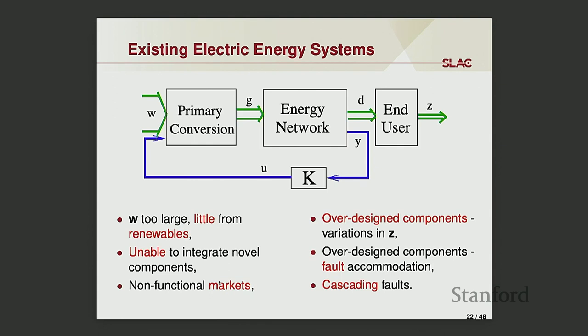Much of the fault accommodation today is done in hardware based on local simple measurements. For example, current has to go 10 times the rated current for some breaker to be triggered to pull out. But if the current is 10 times, that means the forces are also 10 times, or maybe more, depending. So we're talking about huge forces, and that's why substations are so big. People say that if Tesla or Edison were to come back, they would be amazed by many things, but they would recognize substations right away because the spatial size didn't change much.